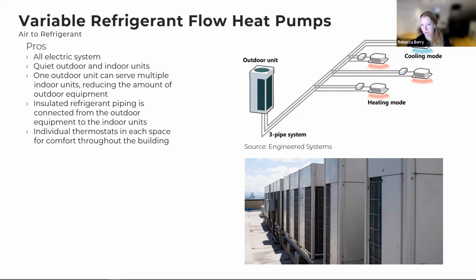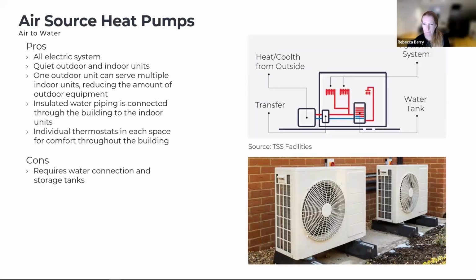You want to go to the next one, Ken? Sure. Okay. Air source heat pumps. So this is an air to water system. What that does is it's able to produce about 130 degree heating water and then 45 degree chilled water. So you would have fan coils within the building that would use either heating water or chilled water to do your heating and cooling. The indoor units are quiet again because the compressors are outside.